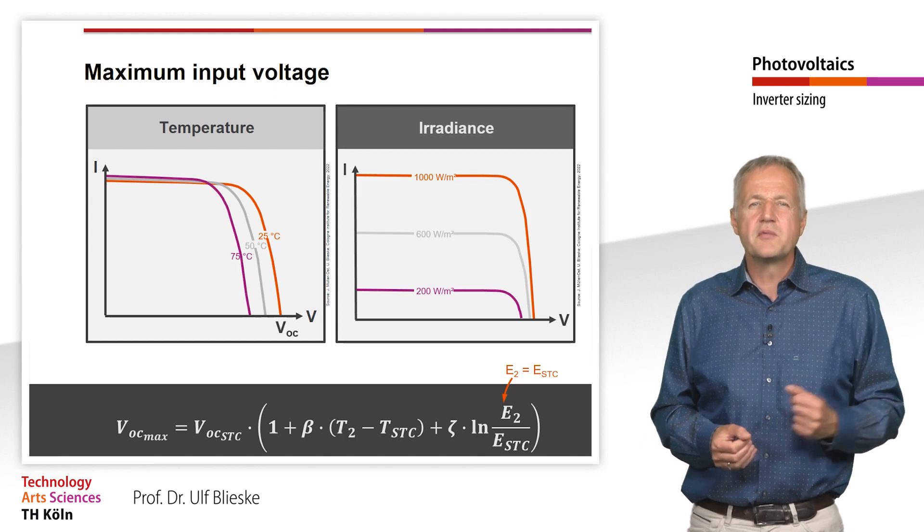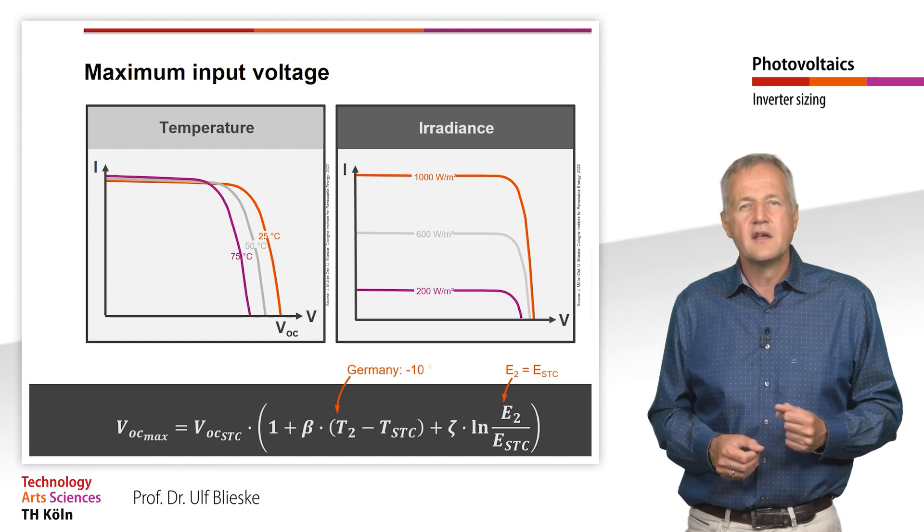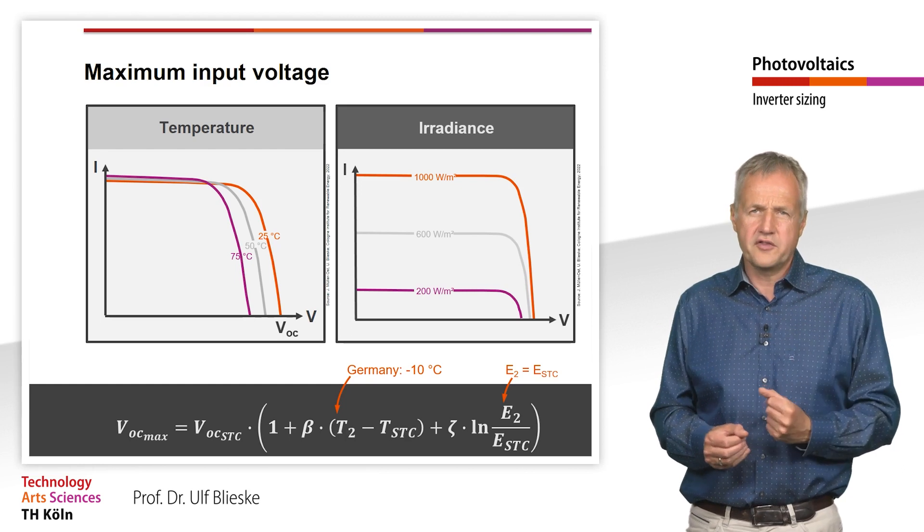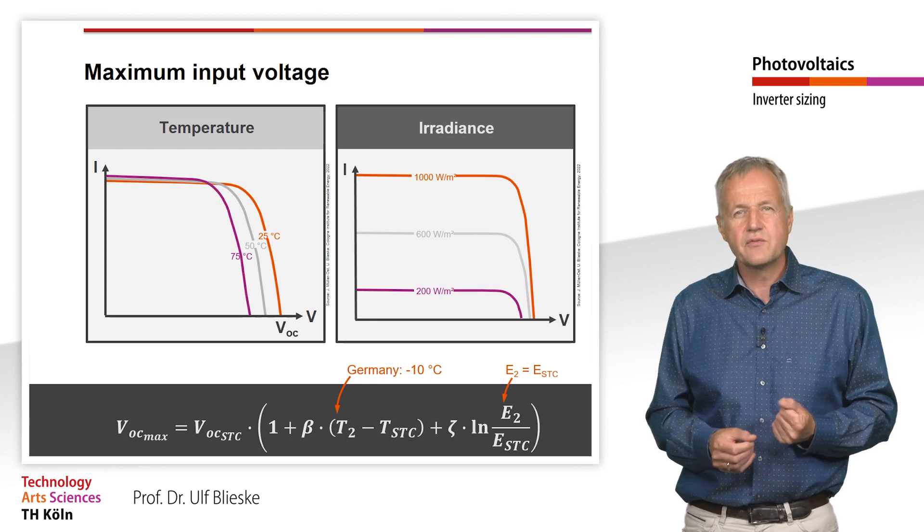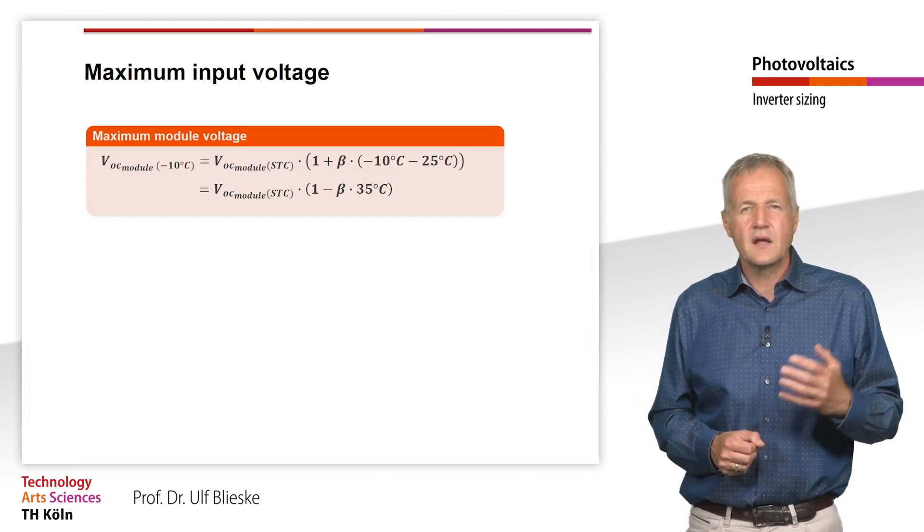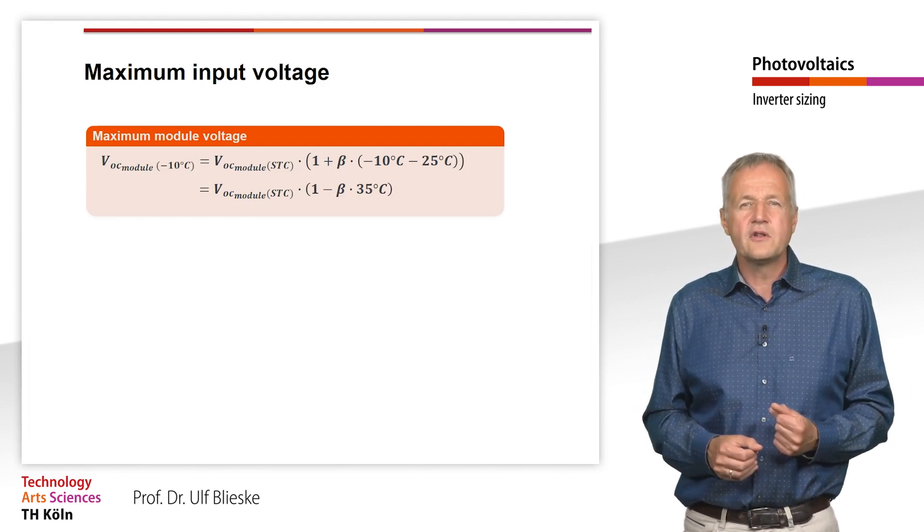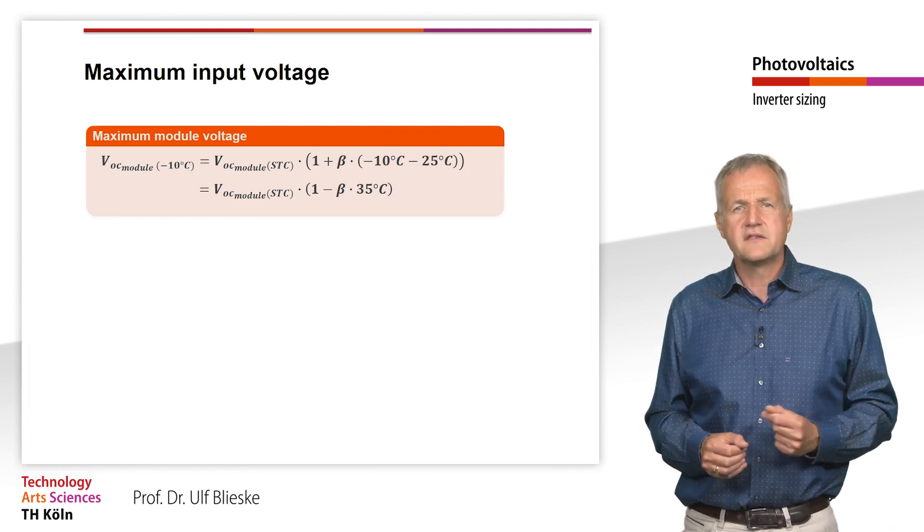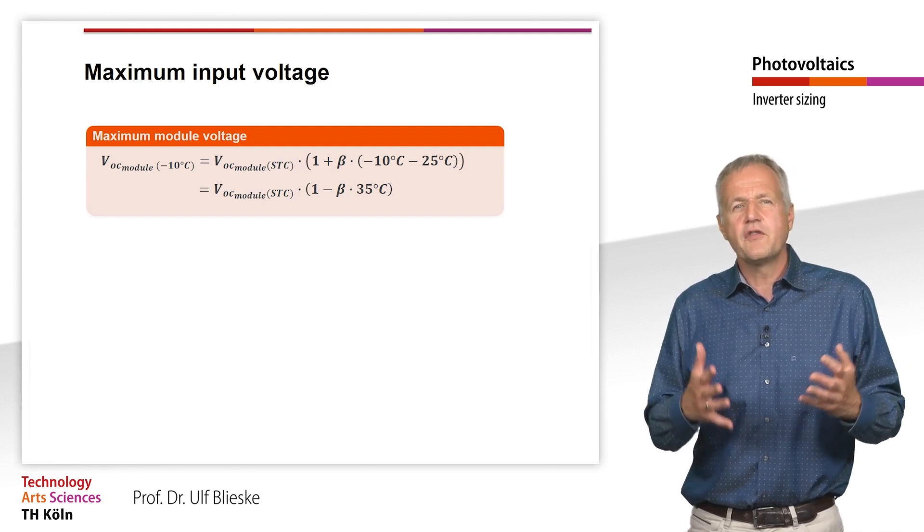For the temperature, a minimum temperature of minus 10 degrees is usually assumed for a plant in Germany. Depending on the location, however, lower temperatures are also possible. For a plant in Helsinki in the north of Europe, a temperature of minus 20 degrees Celsius should be expected. In order to calculate the highest expected open circuit voltage for a specific solar module, we need the open circuit voltage at STC conditions as well as the temperature coefficient beta. Both values can be found in the datasheet of a solar module.